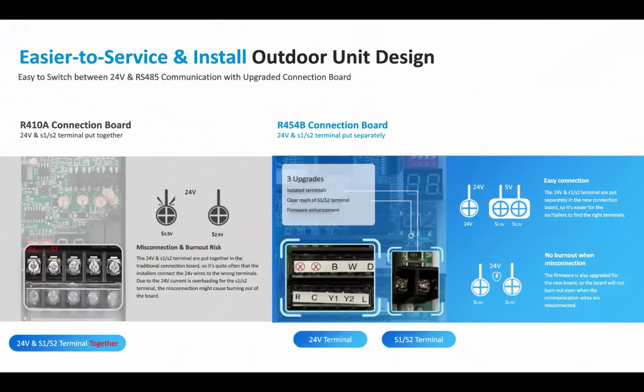Okay, so let's talk about this. So here we go again. S1, S2, they moved them off of that board to keep guys from screwing it up. They also built in voltage protection on it now. So those S1, S2 terminals are actually protected now out to 50 volts. So if somebody does happen to wire 24 volts to those two terminals, it's not supposed to blow the board.